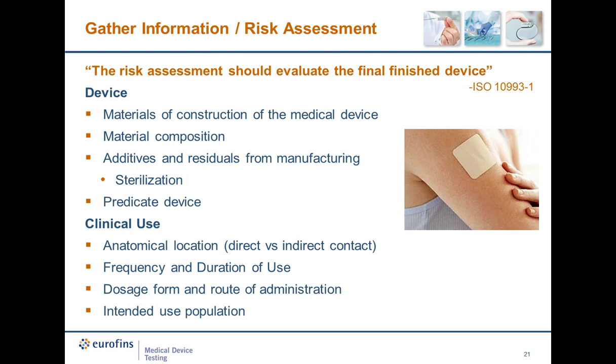After establishing that the device has direct or indirect contact, there is a plethora of information to gather. A sponsor needs to establish the materials of construction and gather as much information on the composition of these materials as possible. If this information is not readily available, sponsors can use qualitative and quantitative methods to determine the composition of the materials, filling gaps where there is incomplete information.